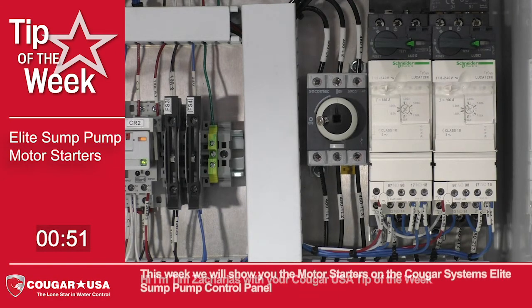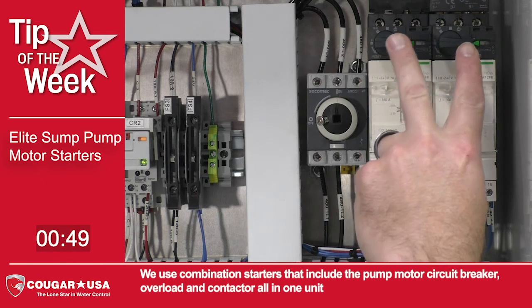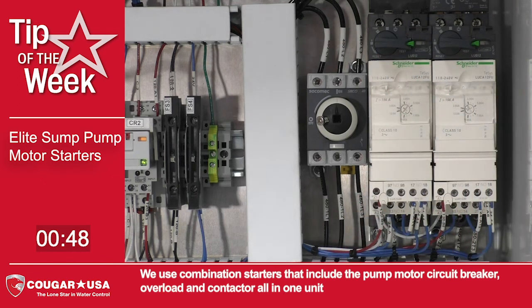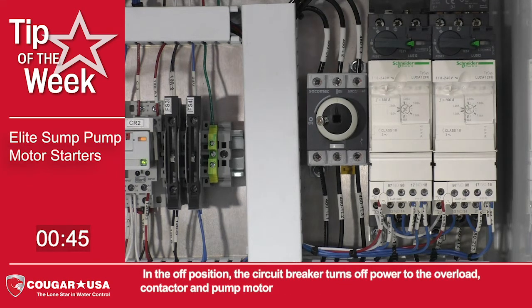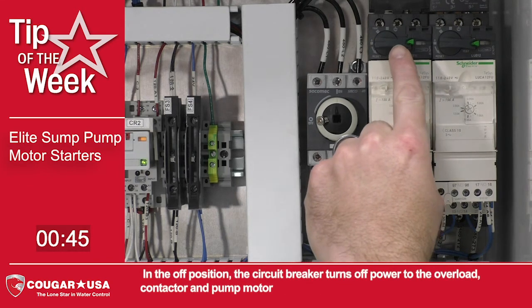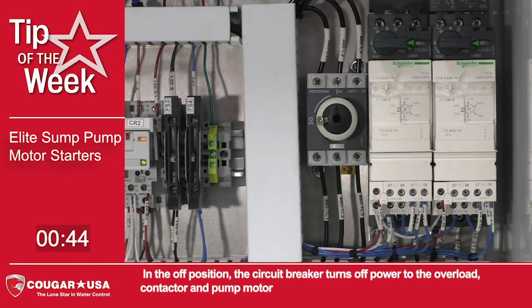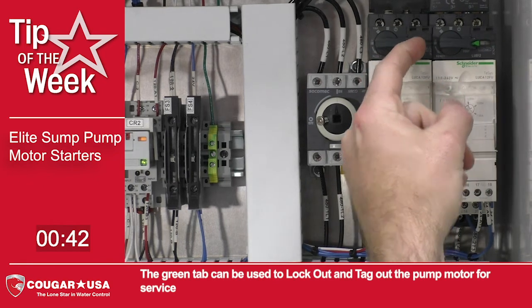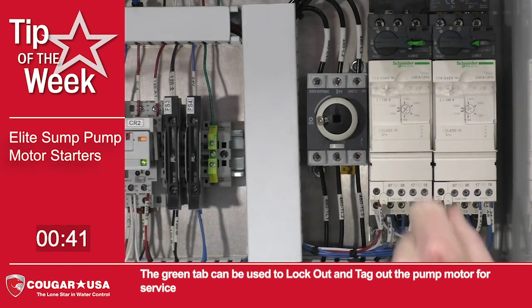This week, we will show you the motor starters on the Cougar System's Elite Sump Pump Control Panel. We use combination starters that include the pump motor circuit breaker, overload, and contactor all in one unit. In the off position, the circuit breaker turns off power to the overload, contactor, and pump motor. The green tab can be used to lock out and tag out the pump motor for service.